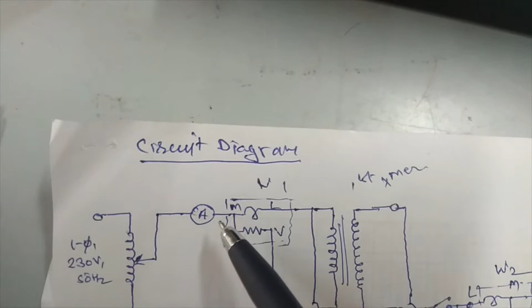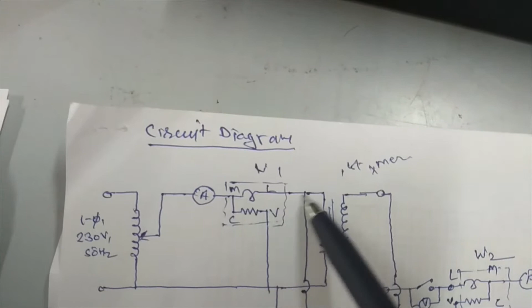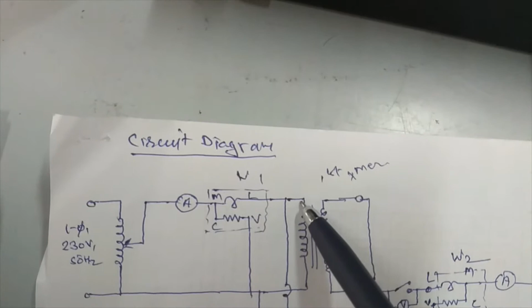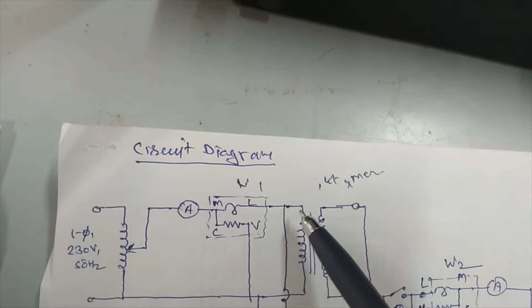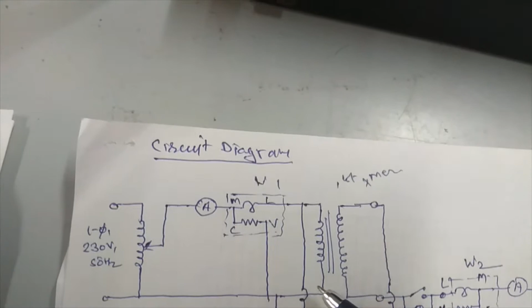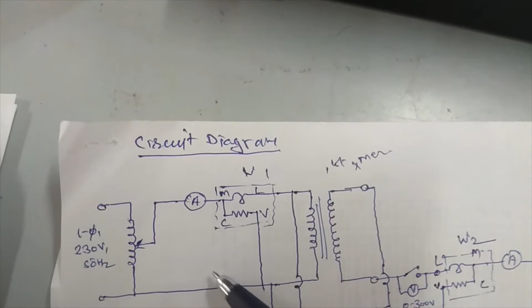The M terminal is connected to the wire coming from the ammeter. The L terminal is connected to the first terminal of the first transformer's LV side, which is the primary. Then M and C are shorted, and V is connected to the other terminal of the transformer, which is also connected to the second terminal of the supply. So this is the primary side connection of one of the transformers.